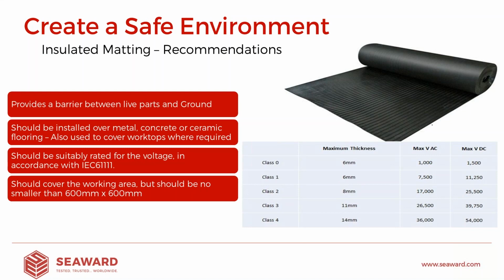There is a size in terms of how small it should be. It should be no smaller than 600 millimeter by 600 millimeter. Again, that just gives enough room for the operator to shuffle from side to side without coming off of the rubber matting when performing the safety testing. This is probably one of the most important elements of creating a safe working environment, particularly for protecting your operators. So we would generally always recommend installing rubber matting into any electrical safe test area.